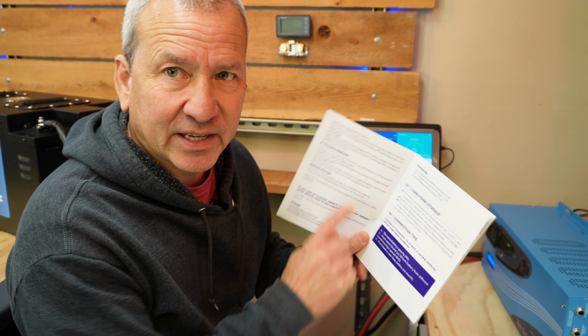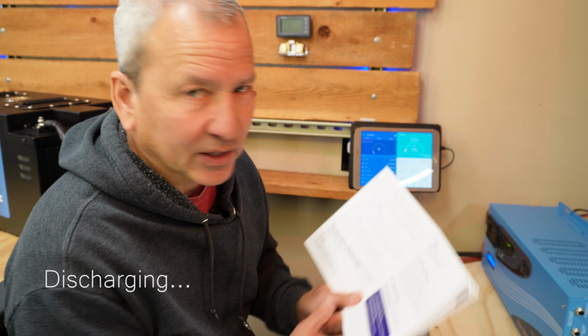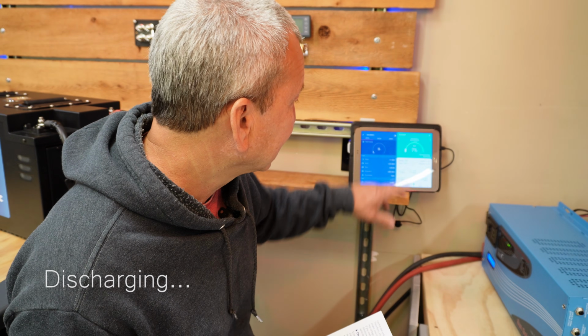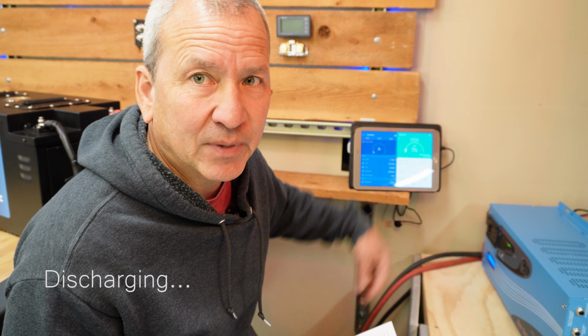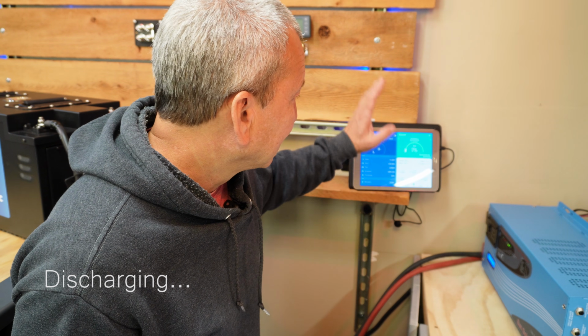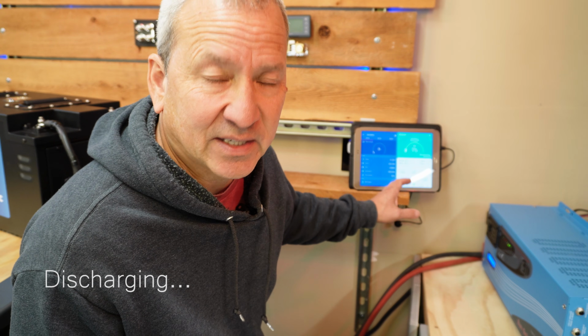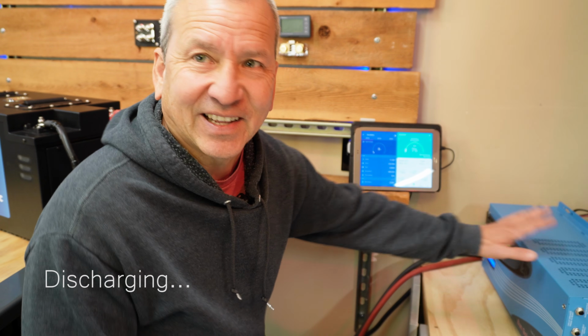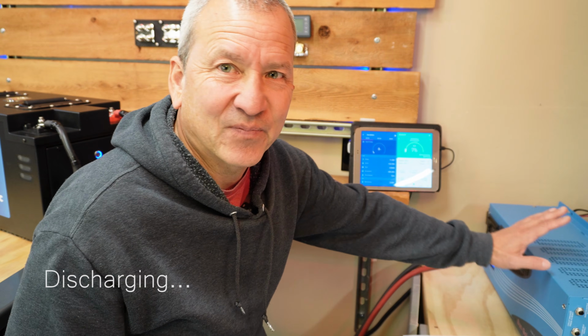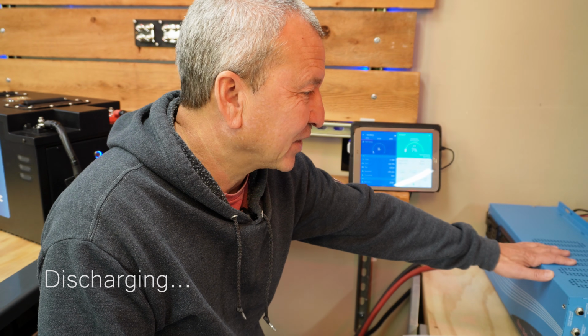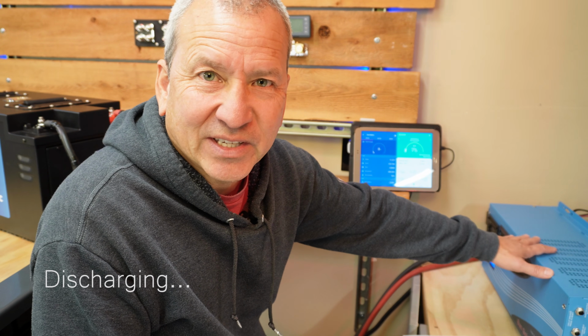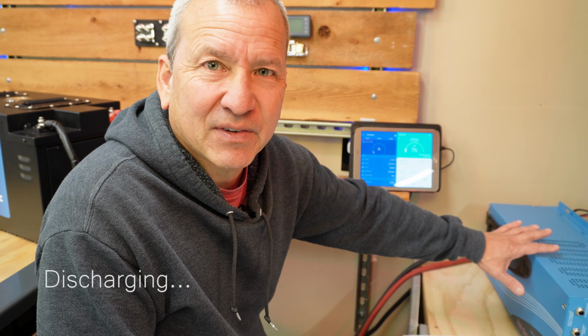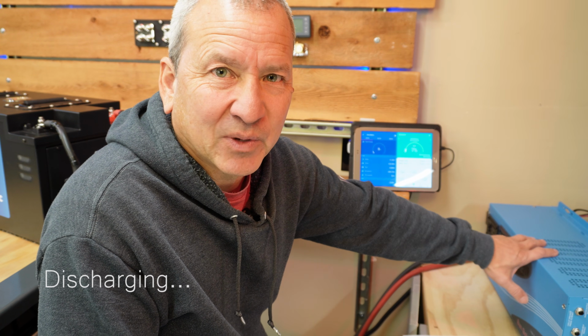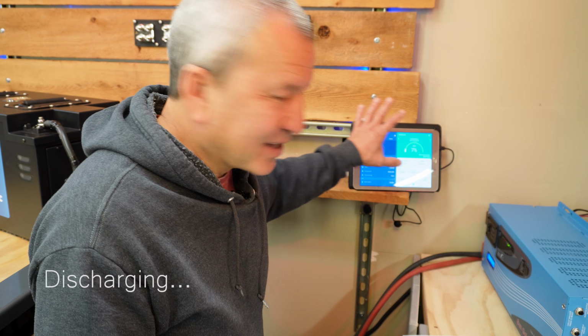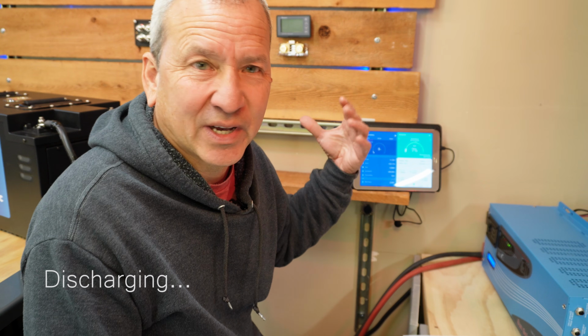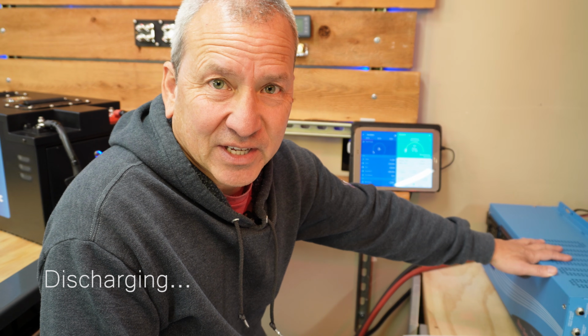Now it says here in the manual that the low voltage disconnect is 10.8 volts, so I'm expecting it to basically drop off once it gets to 10.8 volts. Luckily, I looked up the low voltage cutoff on the inverter, and it's lower than 10.8 - it's like 10.5 or 10.0 volts depending on what you have it set to. So hopefully the battery or the BMS will cut out before the inverter does.